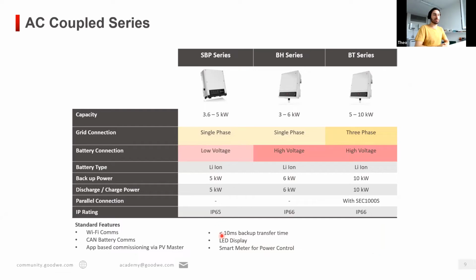And for our AC coupled series, so our battery inverters here, our portfolio is a little bit slimmer. So here we have basically 3 different ones. We have the SBP, which is a single phase inverter compatible with low voltage batteries, so 48 volts batteries. Then we have the BH series. This is between 3 up to 6 kilowatt. Also single phase, but instead is compatible with high voltage batteries. And the last one, the BT, this is sort of like the sibling of the ET that you saw before here. And this goes between 5 up to 10 kilowatt, is a 3-phase inverter and also compatible with high voltage batteries. Exactly like the ET, this is also possible to connect in parallel with this same combination box that I mentioned before.